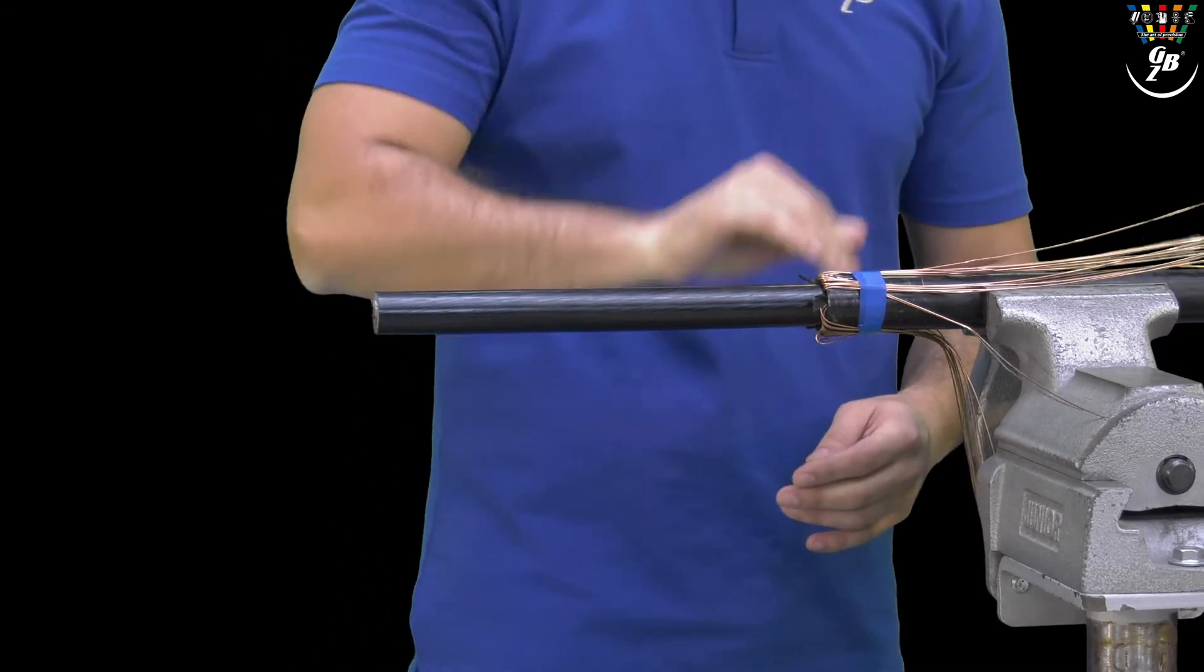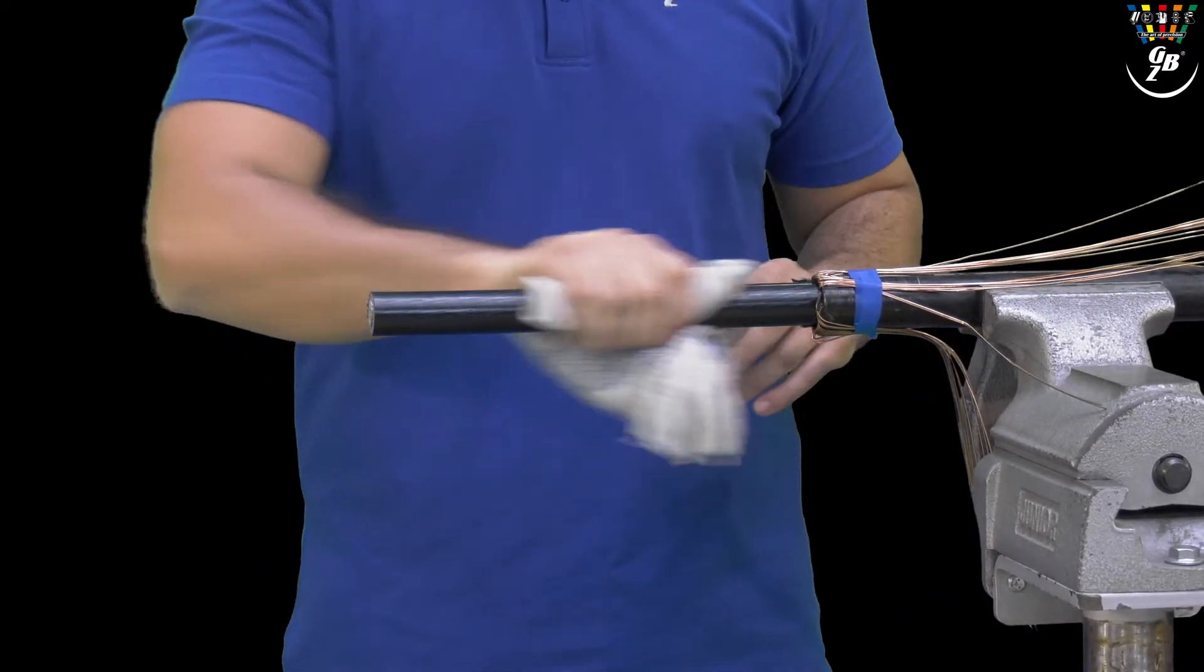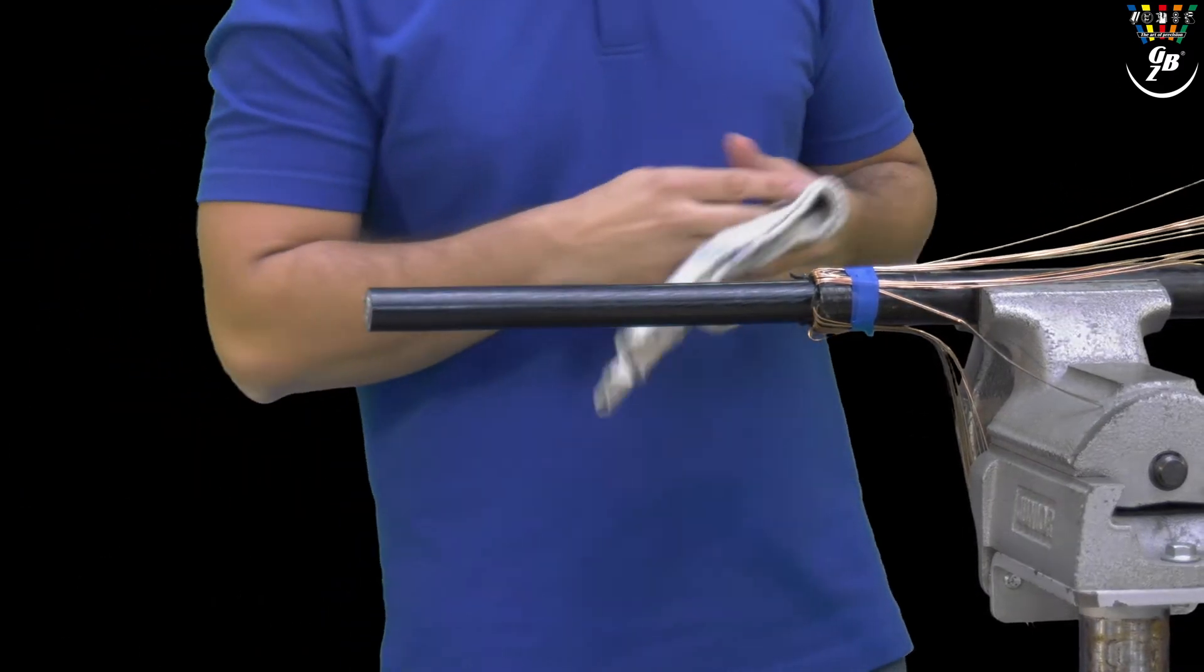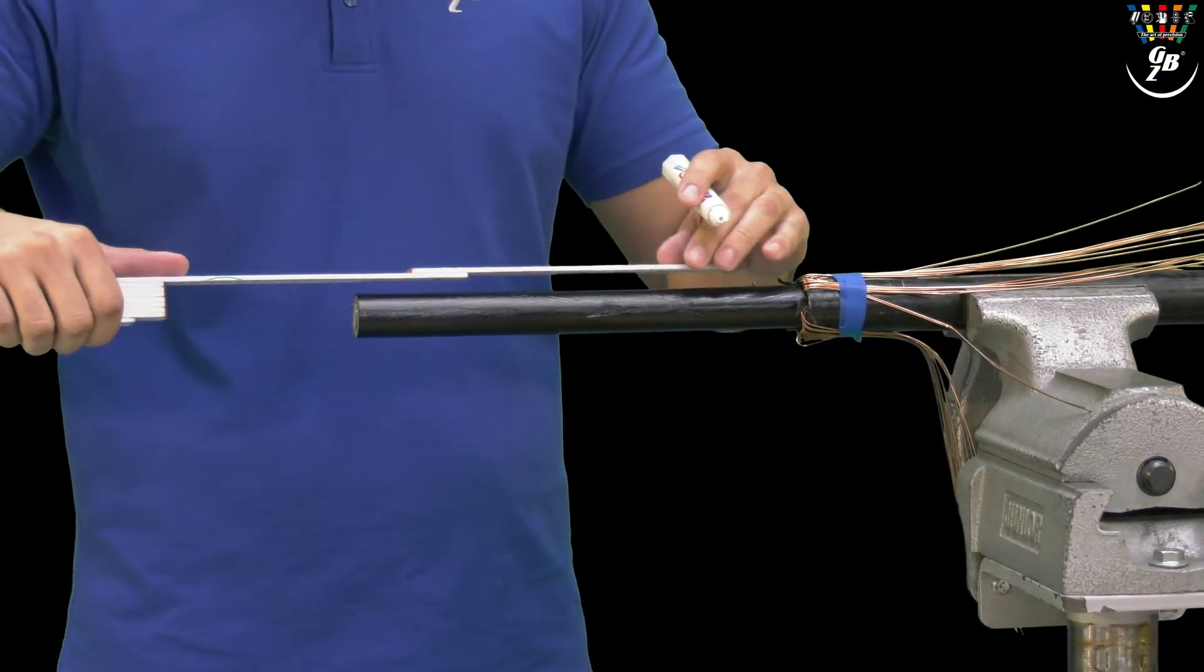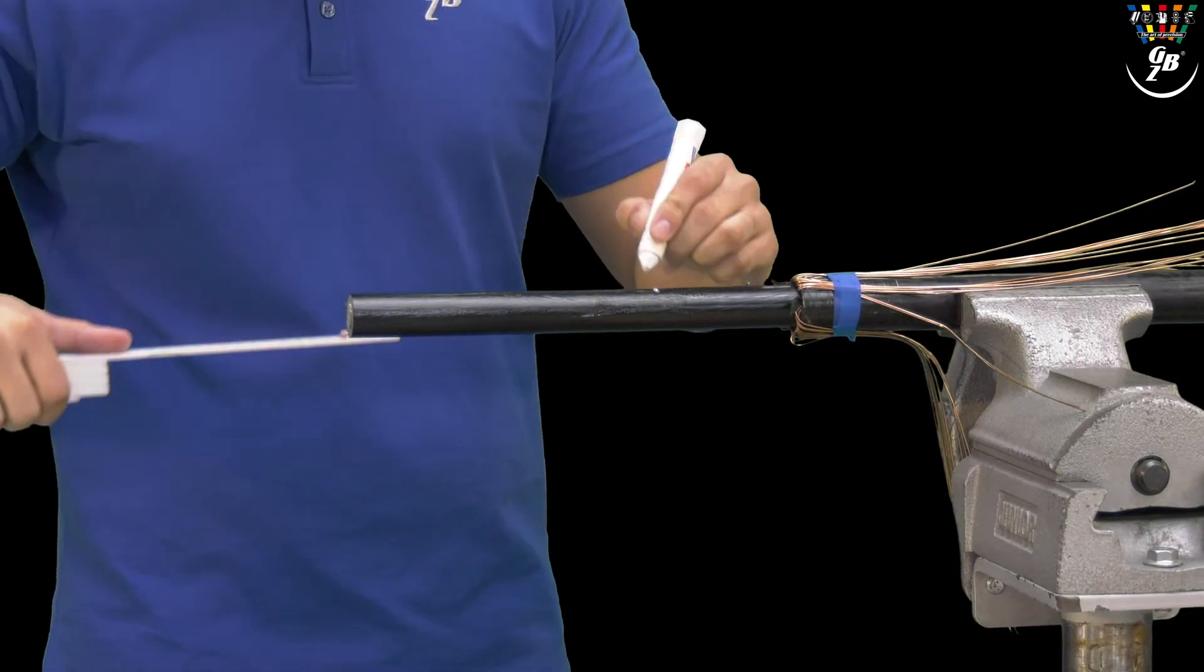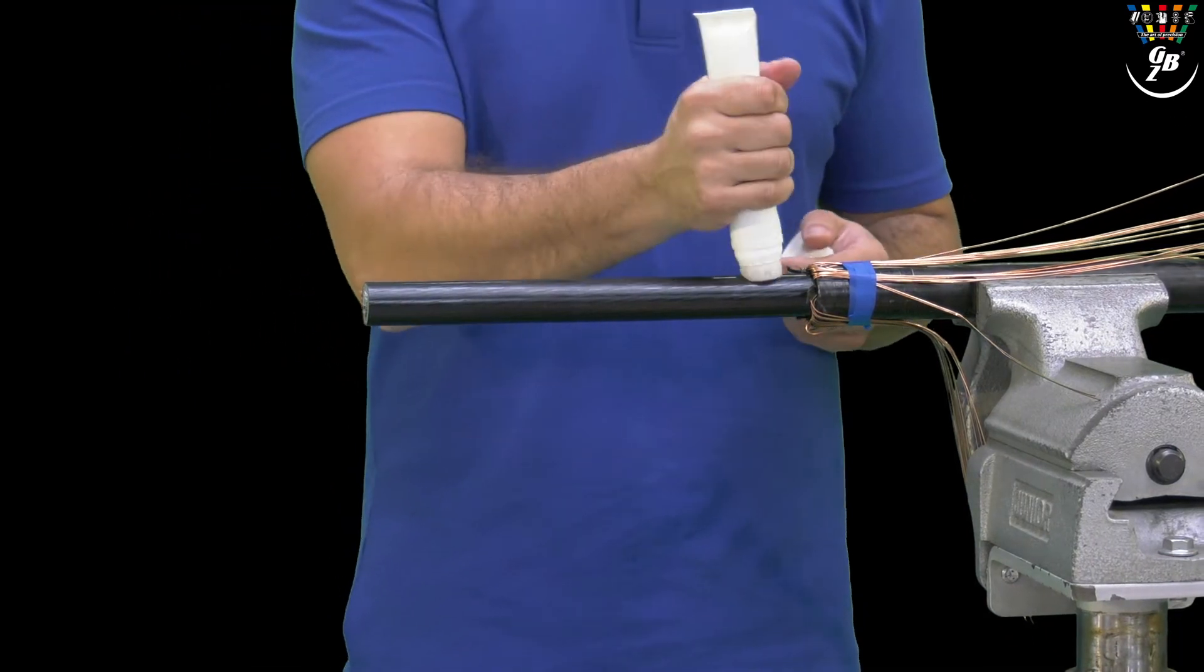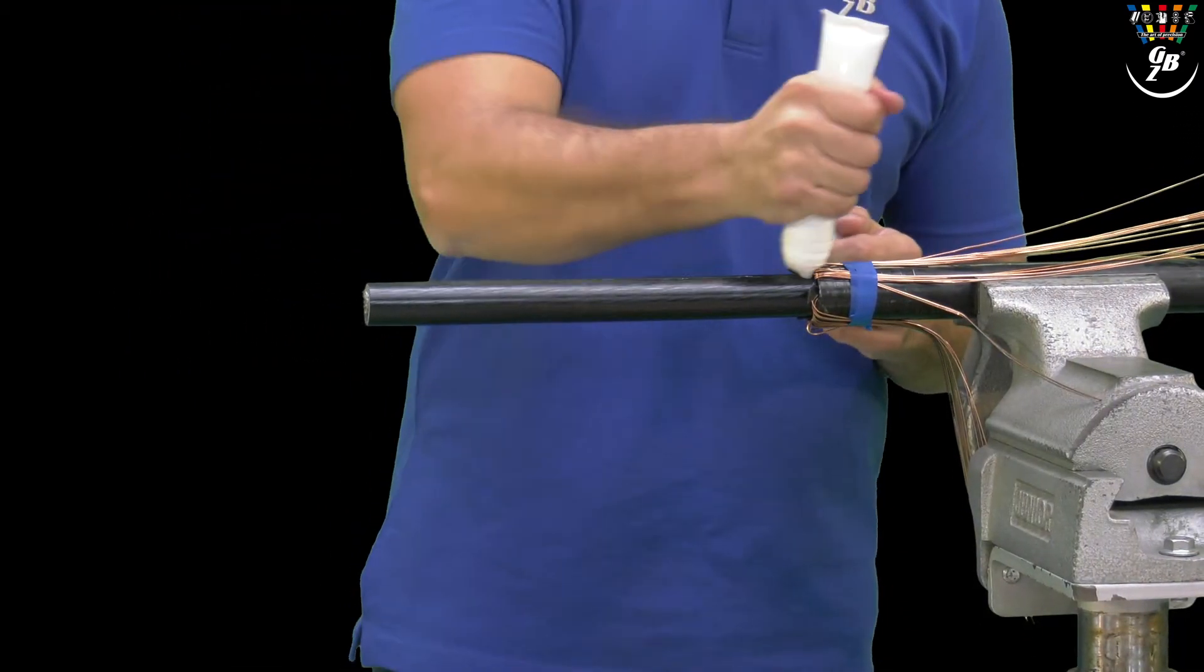We remove the inner conductive layer with the peeling tool GBP20. First we clean the cable. Then the peeling end has to be marked. And finally silicone is applied for better gliding of the tool.